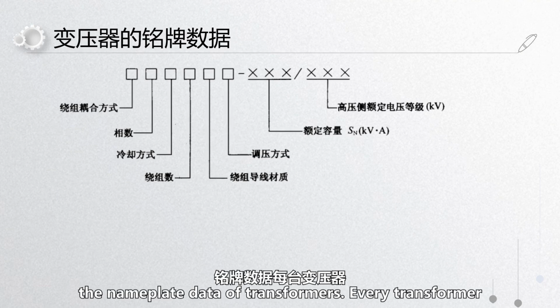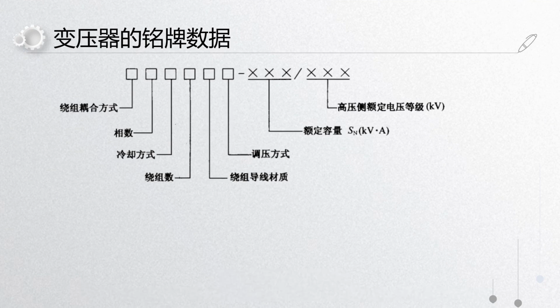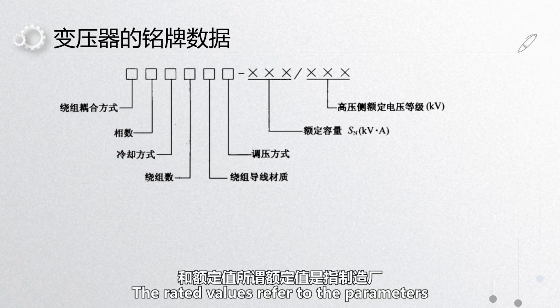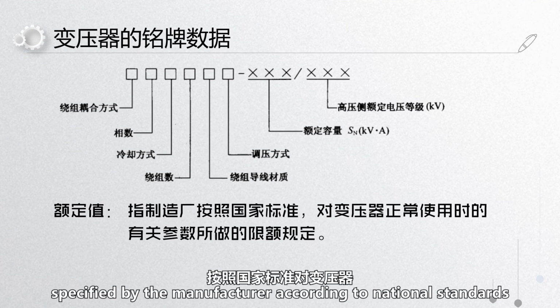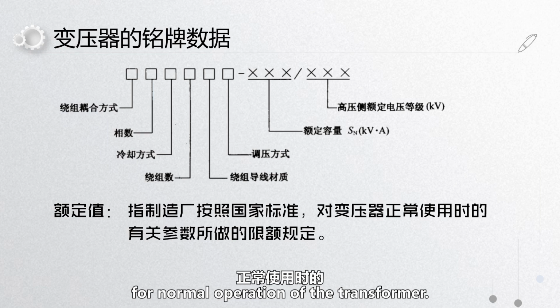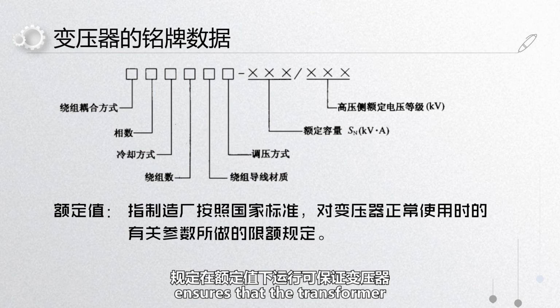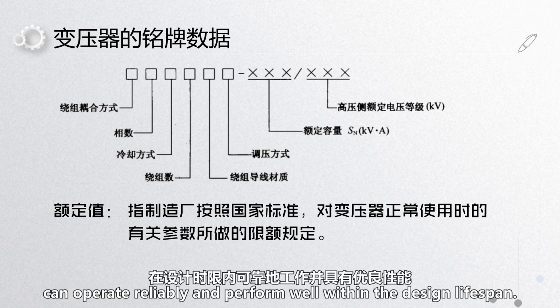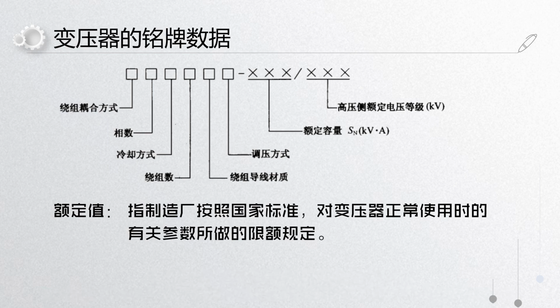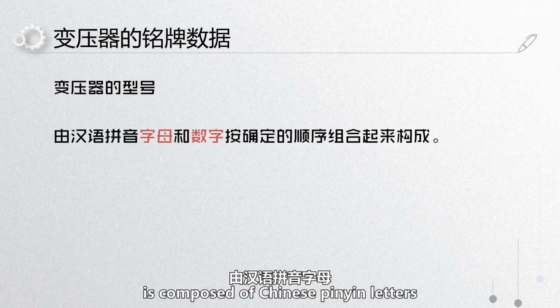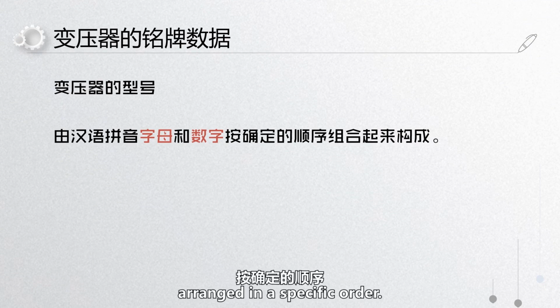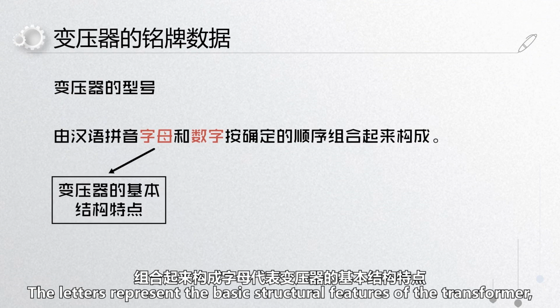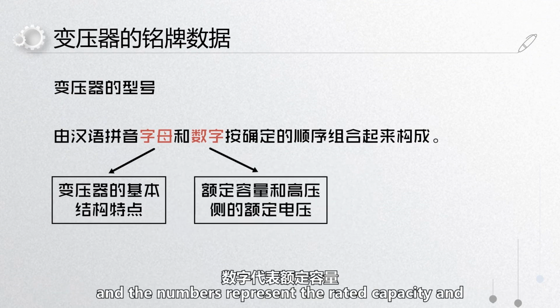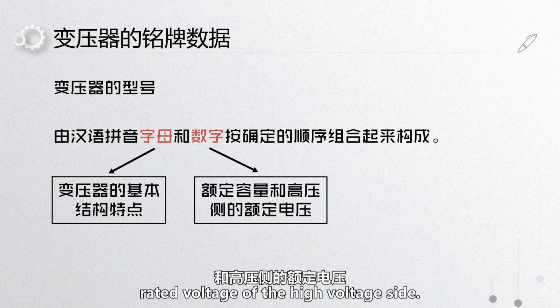Next, we will talk about the nameplate data of transformers. Every transformer has a nameplate in a prominent position, indicating the model and the rated values. The rated values refer to the parameters specified by the manufacturer according to the national standards and for normal operation of the transformer. Operating within the rated values ensures that the transformer can operate reliably and perform well within the design lifespan. The model of a transformer is composed of Chinese pinyin letters and numbers arranged in a specific order. The letters represent the basic structural features of the transformer, and the numbers represent the rated capacity and rated voltage of the high voltage side.